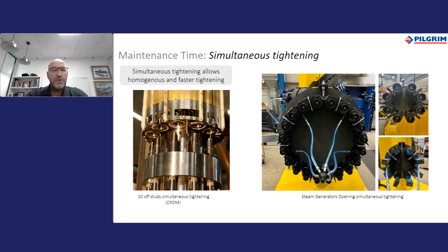To ensure homogenous tightening, we suggest using one tensioner per stud in the form of a tightening ring. The same power unit supplies the complete ring, ensuring the same pressure levels in all tensioners. This can dramatically reduce the time needed to create a fully tightened unit and ensures each stud tightens simultaneously with the exact same force, negating the need for multiple passes to achieve full load — reducing time and operator fatigue. With the inclusion of these innovative Pilgrim design features, your operators can be safer, faster, and more accurate, with no reworking once the job is done. With Pilgrim, it's right — first time, every time.